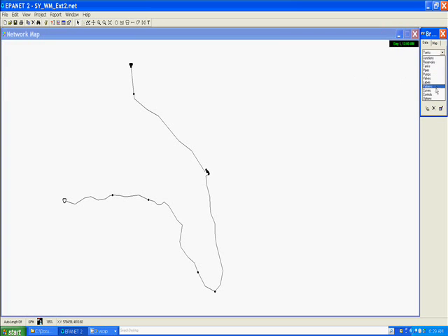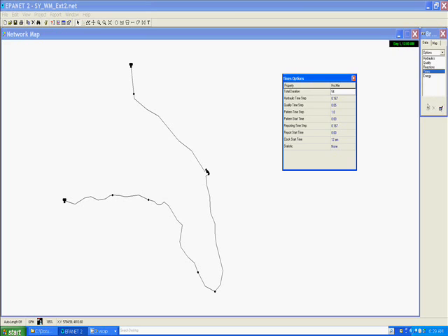We've set our options and the times for this model. Let's just take a look at what we've selected. We've got a duration of 54 hours, which equates to 3 18-hour days. We've got a reporting step for the hydraulics of 0.167. That actually equates to about 10 minutes. I think earlier on I said it was about a 1 minute reporting step. This is actually 10 minutes, and the same for our reporting time step here.